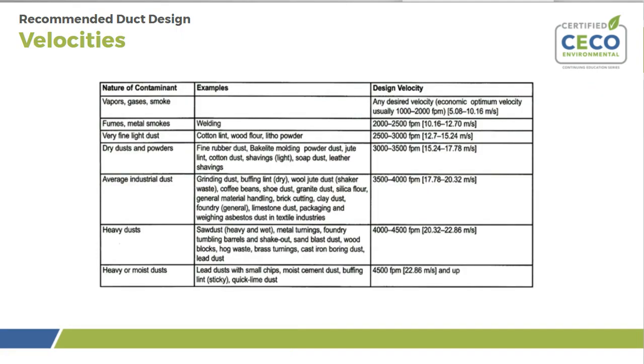For velocity rates, if it's a vapor or a gas or smoke, we can go as low as 1,000 feet per minute. I actually did a project where we were conveying a powdered milk, and we had to go below that number, but typically for fumes and gas and vapor, we're in the 1,000 to 2,000 range. For fumes that have metal smoke in them, for welding, we go in the 2,000 to 2,500 range. For a very light dust, like wood flour or cotton lint, you're in the 2,500 to 3,000 range. For dry dust and a powder, we're in the 3,500 range.